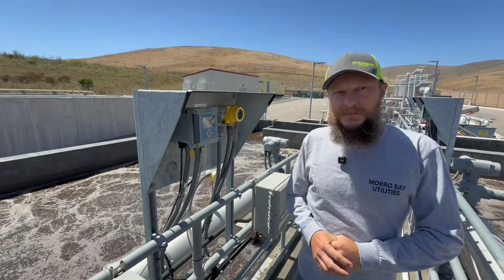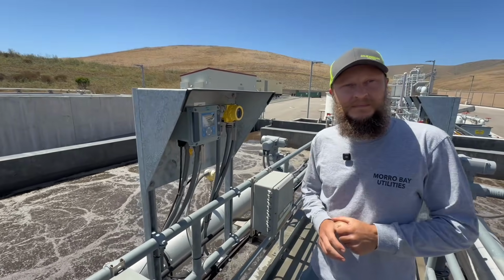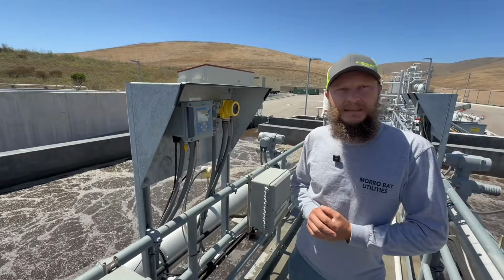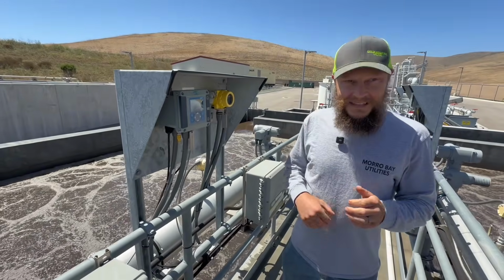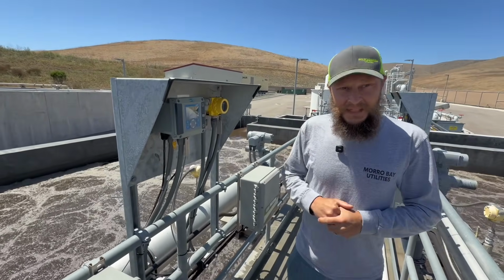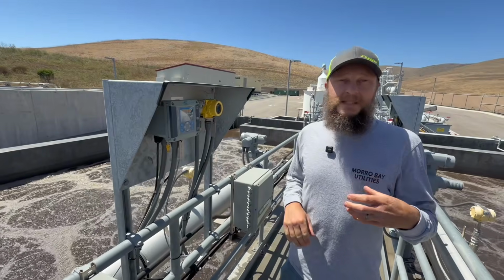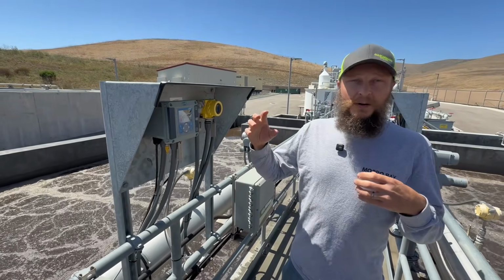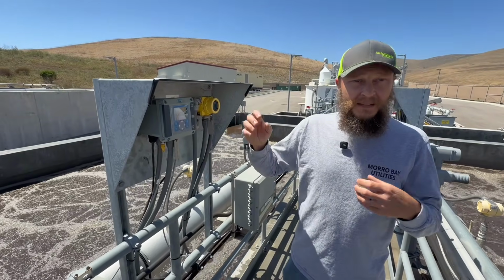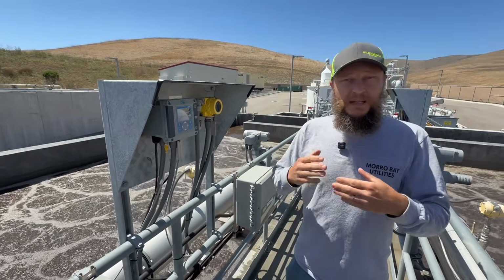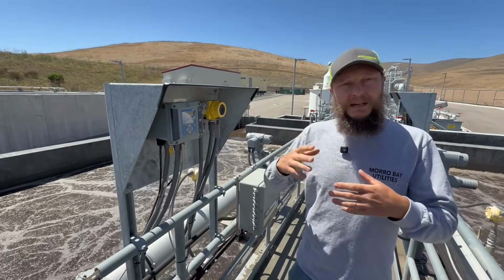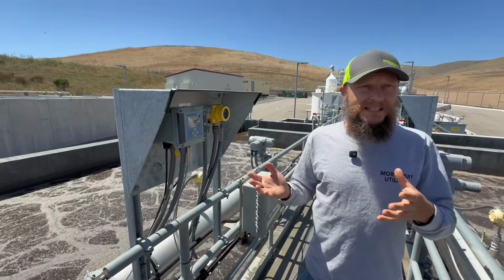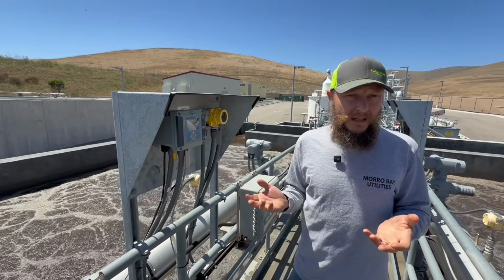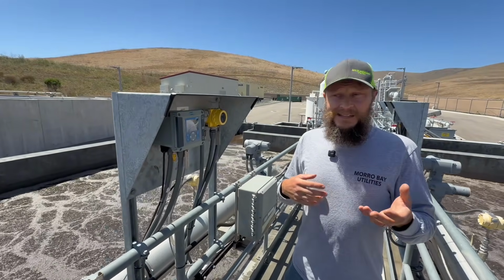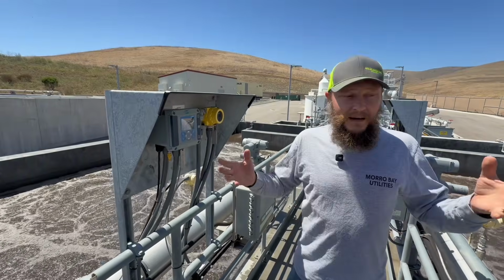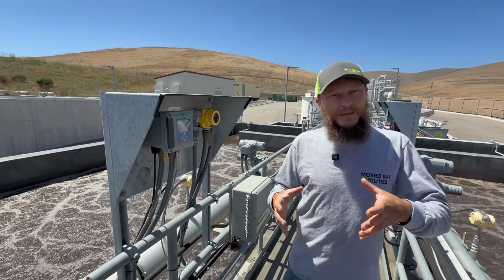And 4 being, let's say, just anecdotally, 0 parts per million, and 20 being 7 parts per million, right? Yes, so long as you're scaled for that. That's right. So 4 milliamps would be 0, and 20 milliamps would be 7, and then it would interpret in between. So you have that 16 milliamp span. And a lot of people might say, hey, why is it 4 to 20 and not just 0 to 20? Because it's kind of like that riddle of why are manholes round? Right.